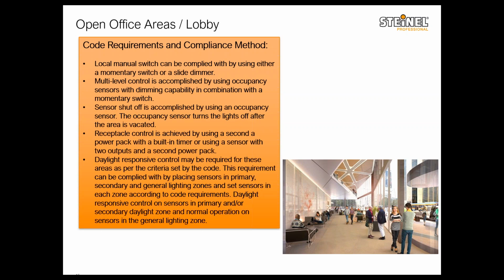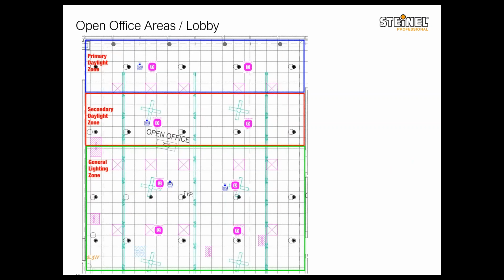And the load requirement for Title 24 is actually 120 watts in or partially in the primary daylighting zone. So if you look here, again, this is an example. It's not necessarily accurate or representing an exact case, but I've taken the layout from one of our projects in California, so we can do it to some extent.